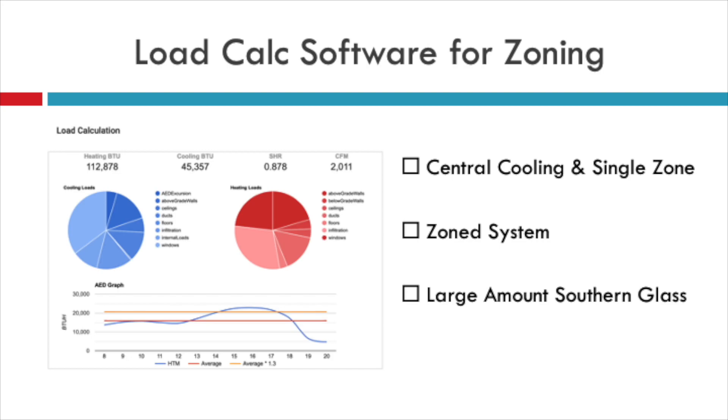When selecting load calc software for zoning, there are a few key features to look for. Number one, it needs to provide an AED graph — at least for the block load. Hopefully it can provide that AED graph for each zone as well. If not, this may require multiple load calculations in your software. As you can see in this particular AED graph, there's a lot of glass facing south. If I wanted to zone this system, I'd have to go back and do a separate load calc for each zone to confirm compatibility.